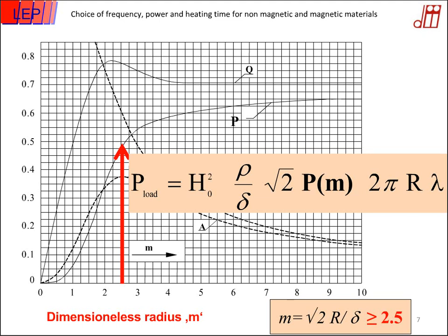Typically, in order to increase M — which depends on the ratio between the radius and the skin depth — we have to increase the frequency. So for small workpieces, when R is smaller, we need a small skin depth, and we need to increase the frequency in order to achieve a value of M of at least 2.5.